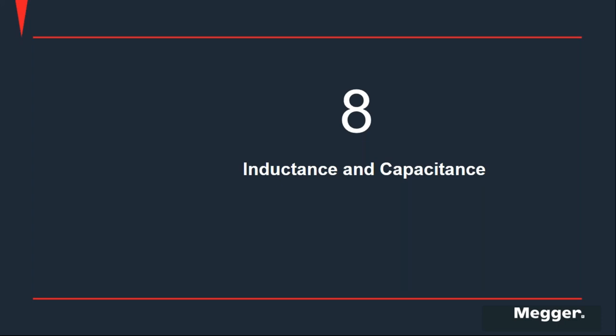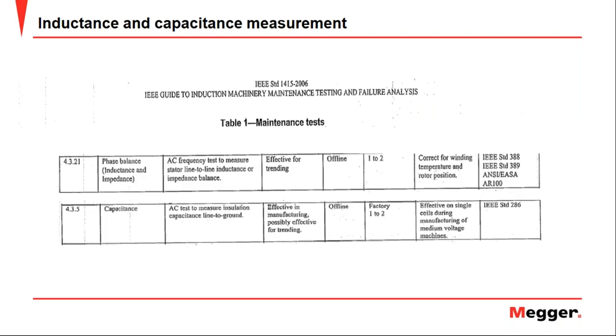Inductance and capacitance. Let's see. Here we can see an extract from the standard for these two variables. The IEEE 1415 standard states that although they can deliver a large amount of information, they are only useful if we build a trend analysis. And I have to emphasize this aspect, only by trend. If we make a single measurement of inductance and capacitance, this value doesn't indicate the insulation condition. Only through an inductance and capacitance trend can we make an accurate analysis of the motor insulation condition.